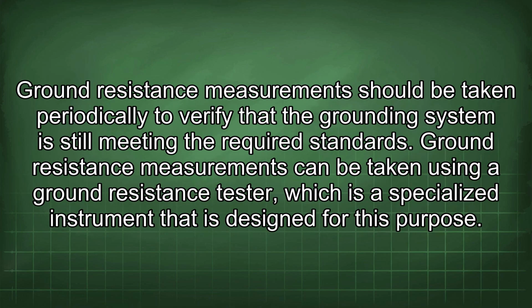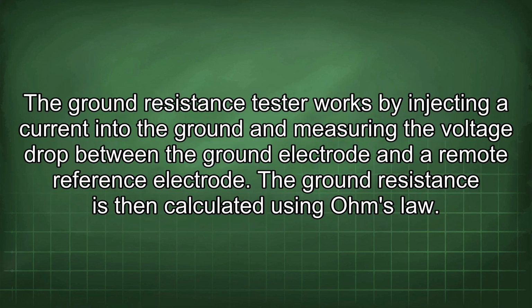Ground resistance measurements should be taken periodically to verify that the grounding system is still meeting the required standards. Ground resistance measurements can be taken using a ground resistance tester, which is a specialized instrument designed for this purpose. The ground resistance tester works by injecting a current into the ground and measuring the voltage drop between the ground electrode and a remote reference electrode. The ground resistance is then calculated using Ohm's law.